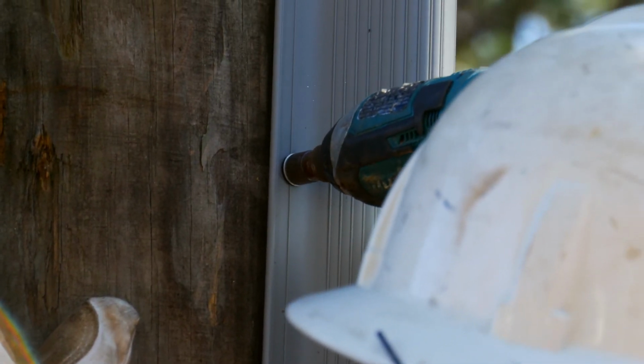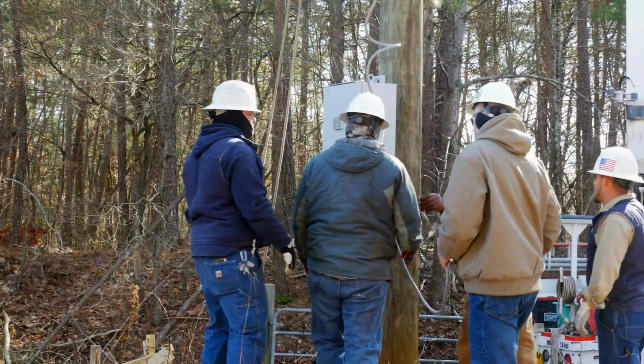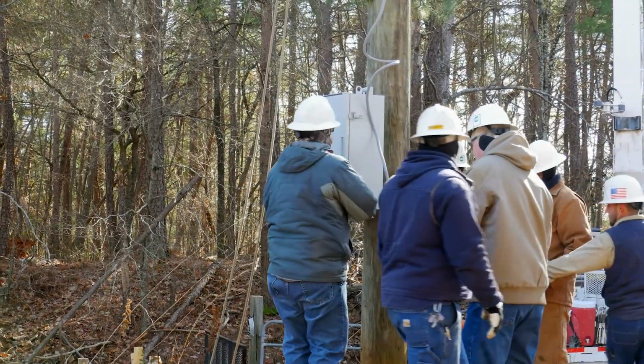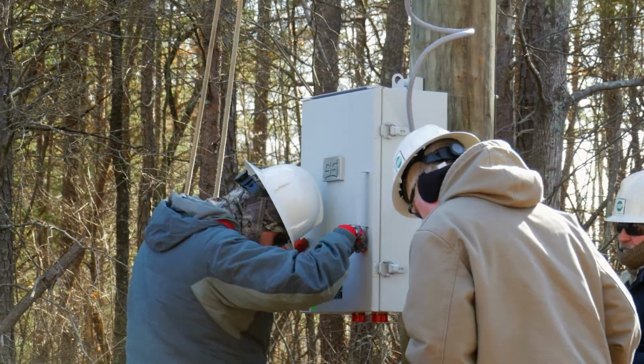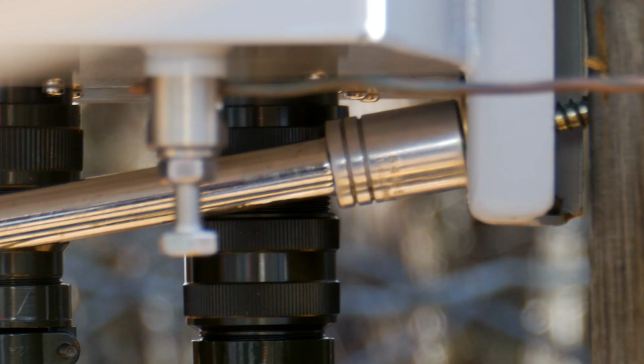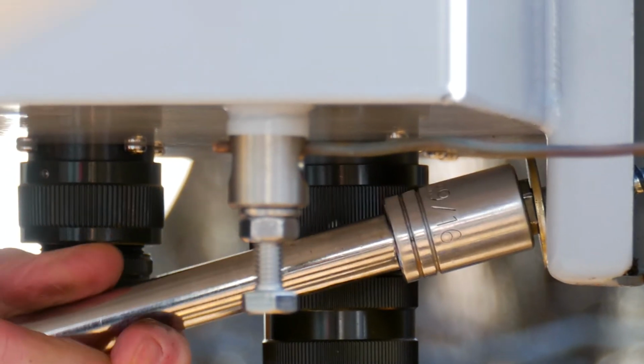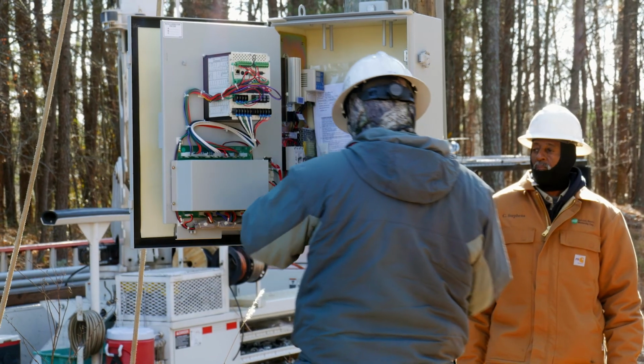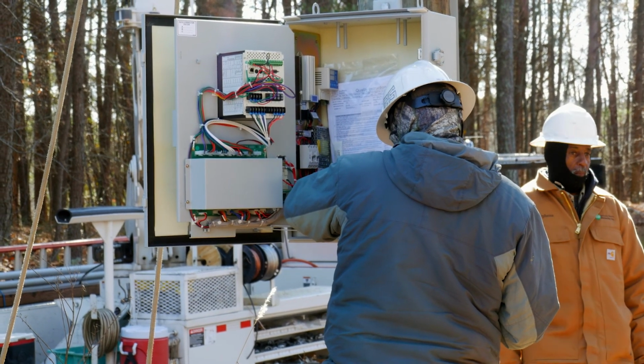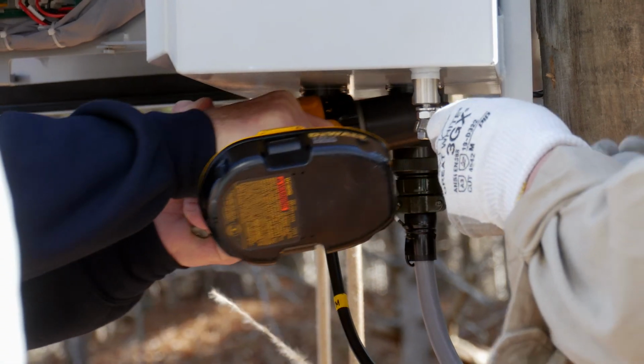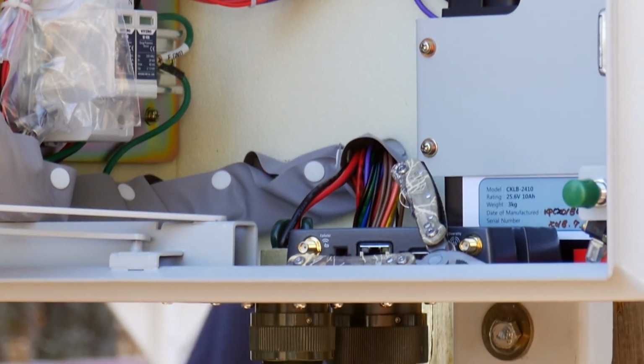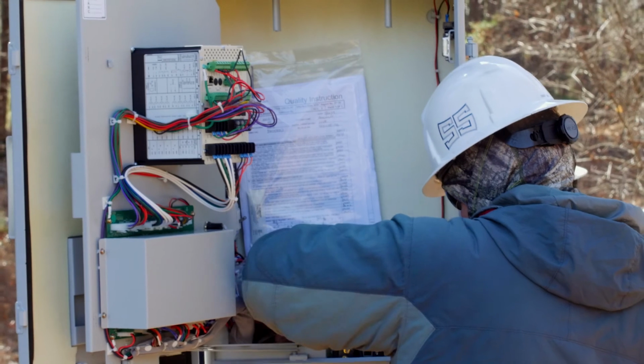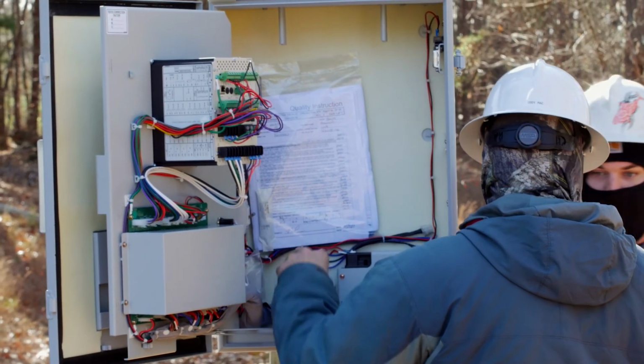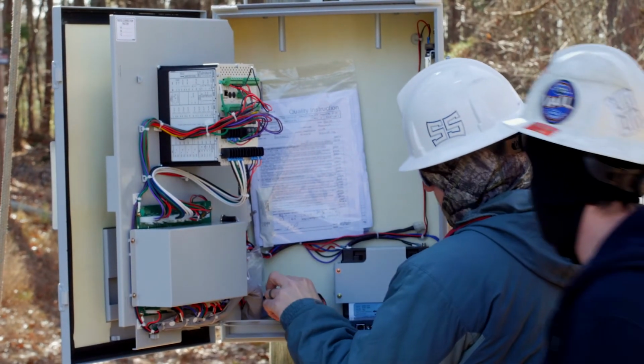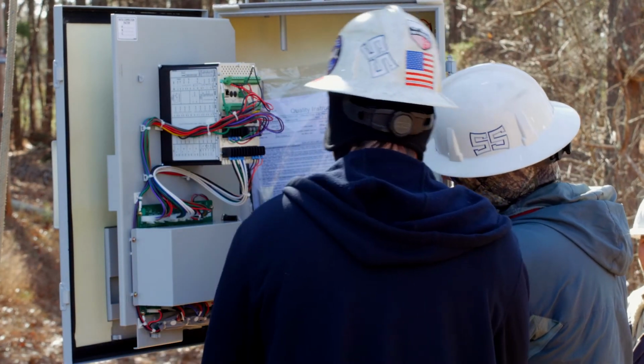and the power cable is now connected to the transformer. With pole mounting provisions on the cabinet itself, installing the control cabinet on the pole at an adequate height is simplified. Once hung, the connectors are tightened and the cabinet is secured to the pole. The grounding wire can then be run to the cabinet's ground lug. Once the ground wire is connected, the control and power cable can also be connected to the bottom of the control cabinet. The breakers inside can now be turned on, providing power to all the components inside the cabinet as well as the recloser itself.